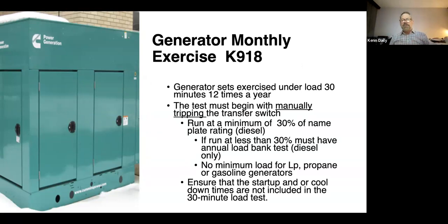Diesel generators are required to run no less than 30% of the nameplate rating of the device. So that's why you have to calculate that every month, to see what percentage of your load you're running. Non-diesel generators, so gasoline, natural gas, or propane generators, have no minimum load the way diesel does. And the only reason diesel does is they don't want to have wet stacking.